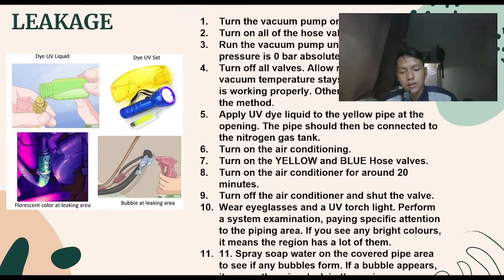If you see any bright colors in the piping area, it means that the region has a leak. And then the last step is to spray soapy water to cover the pipe area to see if any bubbles form. If bubbles appear, it means that there is a leak.